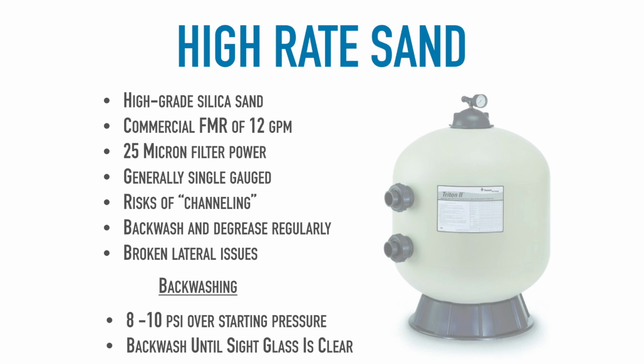Instead, we now have a scientific understanding of how we do this. We backwash when that pressure gauge goes 8 to 10 psi over start, and we backwash simply until that sight glass goes clear. Once it goes clear, you can go back into regular filter mode and you're good to go.